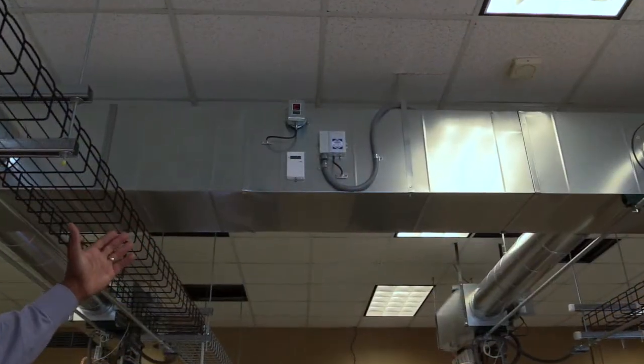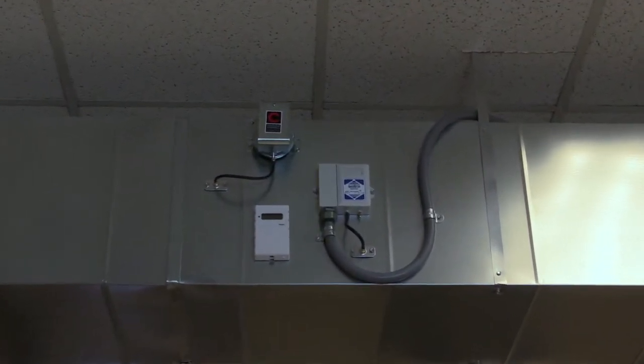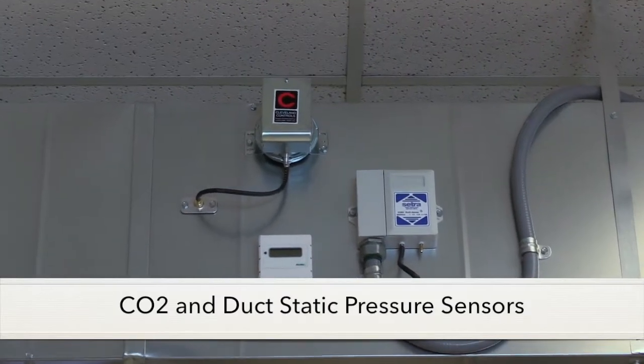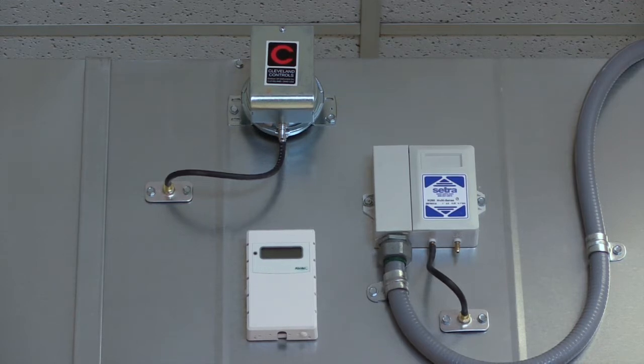You see three various sensors mounted on the duct, all networked back to our main systems controller. One senses duct static pressure, one can sense CO2. If the static pressure is not where it needs to be, the signal is read back at our main controller, which can either ramp our main fan motor up or down based on the static pressure sensed in the ductwork.